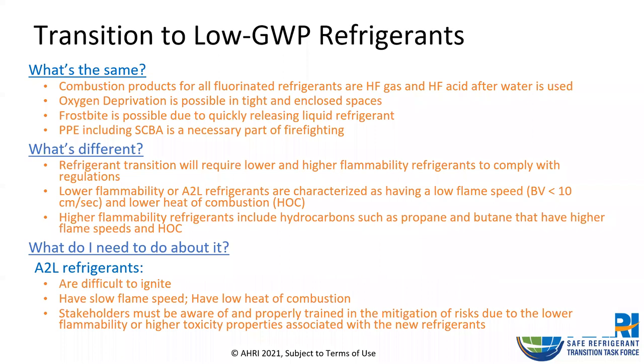So let's talk a little bit more about this transition to low GWP refrigerants. What's the same? Well, the refrigerants are primarily fluorinated refrigerants. So combustion products for all fluorinated refrigerants are HF gas and HF acid after water is used. Oxygen deprivation is also possible in tight and enclosed spaces. Frostbite is possible due to quickly releasing refrigerant, and PPE, including SCBA, as a necessary part of firefighting. So that's all the same when we transition to the new lower GWP refrigerant.